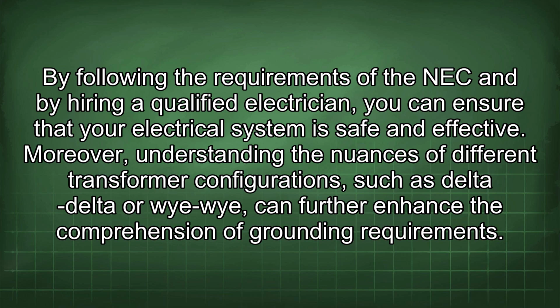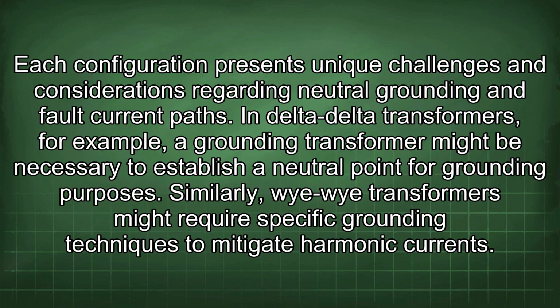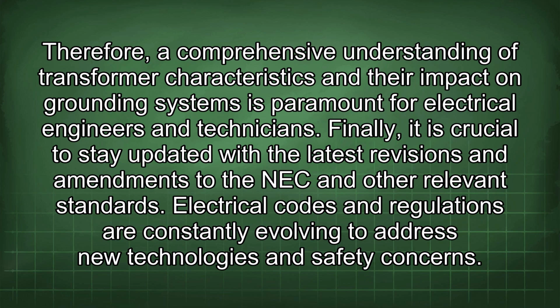Moreover, understanding the nuances of different transformer configurations, such as delta-delta or Y-Y, can further enhance the comprehension of grounding requirements. Each configuration presents unique challenges and considerations regarding neutral grounding and fault current paths. In delta-delta transformers, for example, a grounding transformer might be necessary to establish a neutral point for grounding purposes. Similarly, Y-Y transformers might require specific grounding techniques to mitigate harmonic currents. Therefore, a comprehensive understanding of transformer characteristics and their impact on grounding systems is paramount for electrical engineers and technicians.